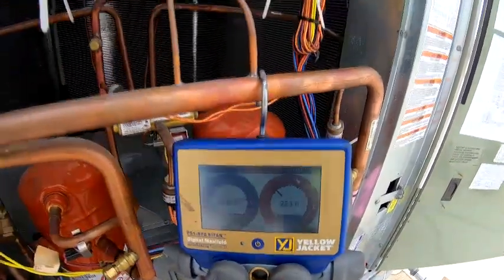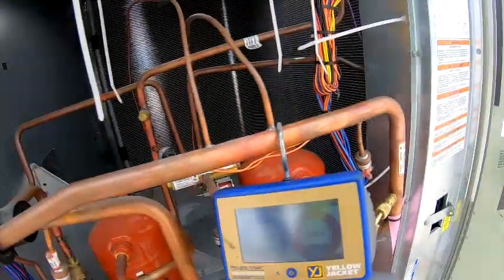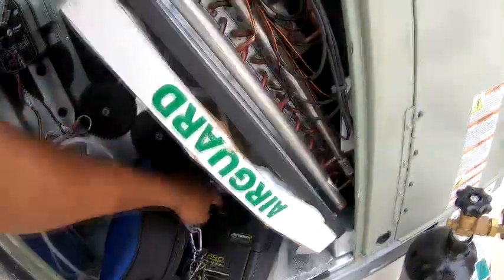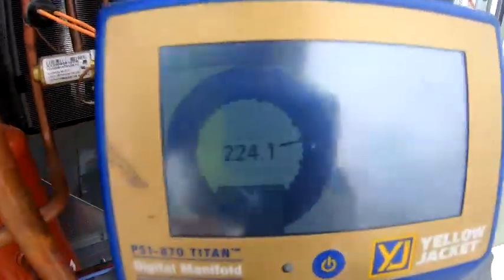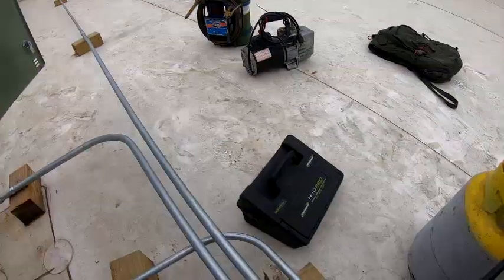Alright, like I said, I did find the leak. You see I got 223. I had 180 PSI of nitrogen only and couldn't find a leak. So I was gonna get the electronic leak detector out and put some trace gas in there, which I did. I raised the pressure to 224 before I pulled the leak detector. I haven't used the leak detector yet.